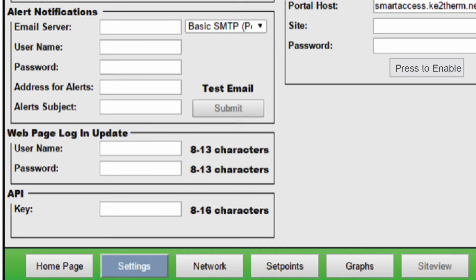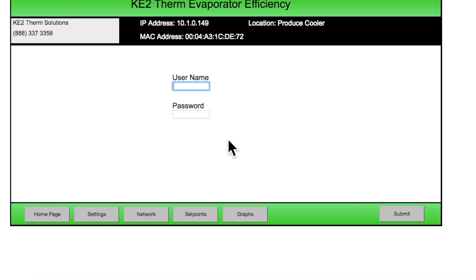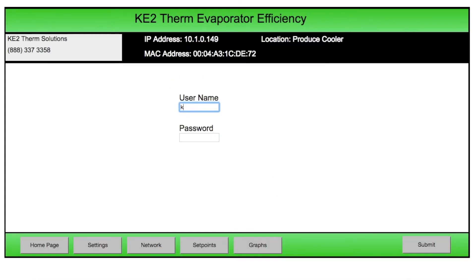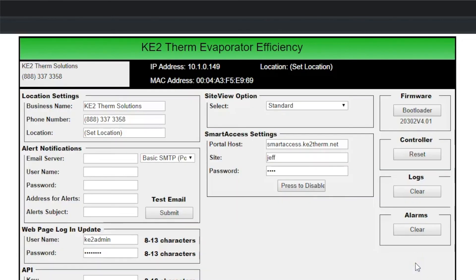Now click on the settings button. Click log in to get the password screen. If the controller is using older firmware, version 3.2 or older, there is only a password and the default is 2222. For versions 3.2 and newer, you'll need to use a username and password. If the controller is still using the factory defaults, username and password are both ke2admin, all lower case. As a side note, we recommend changing these from the default for security reasons. Click the enter or submit button and we are now back on the settings page. Look at the upper right-hand corner of the page for the current firmware version number.